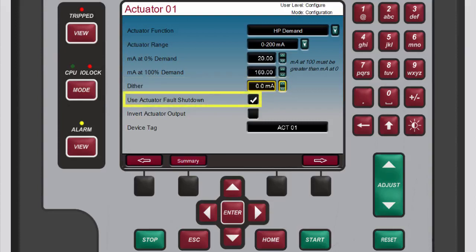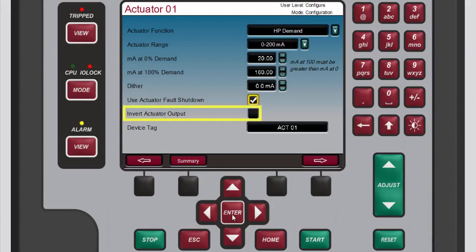To finish configuring actuator 1: the use actuator fault shutdown box contains a check mark by default, which tells the 505 to issue a trip whenever an actuator fault is detected. If you remove the check mark from this box by selecting the box and pressing enter, an actuator fault alarm will be issued without a shutdown. The unit identifies an actuator fault if the current drops below or goes above the failure levels, essentially checking for an open or short circuit in the actuator wiring or coil.